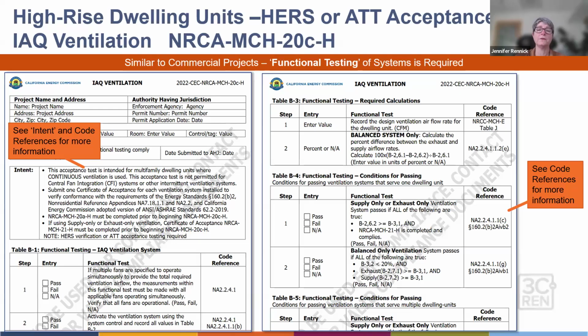Okay, for the high-rise dwelling units, even though we don't have a HERS registry, the HERS or acceptance testing technician, ATT, is to come out and also look at the fan function for continuous outside air and your bathroom and kitchen exhaust. And I put these forms in here as an example and kind of give you an idea of what they look like. But mostly what I'm seeing is that if you're an architect, the forms are handy to look at because it gives you kind of a checklist of things that you might want to include in your drawings, or at least give you a better idea of what you're looking at.